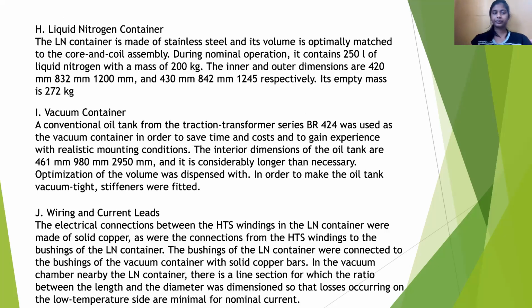Liquid nitrogen container. The LN container is made of stainless steel and its volume is optimally matched to the core and coil assembly. During nominal operation, it contains 250 liters of liquid nitrogen with a mass of 200 kg. The inner and outer dimensions are 420 mm, 832 mm, 1200 mm, and 430 mm, 842 mm, 1245 mm respectively. Its mass is 272 kg.